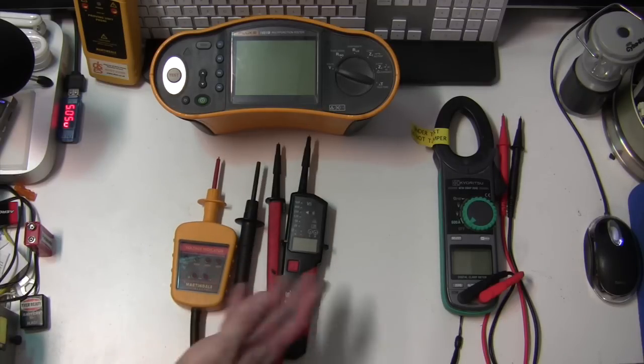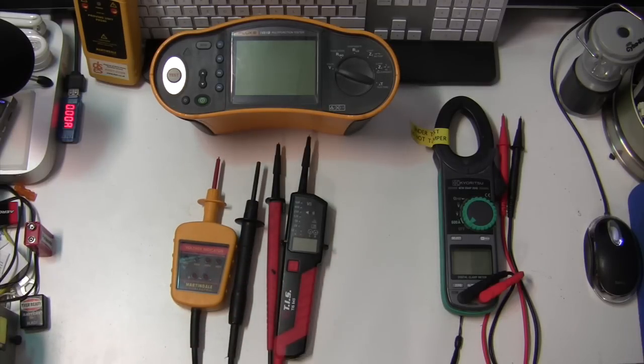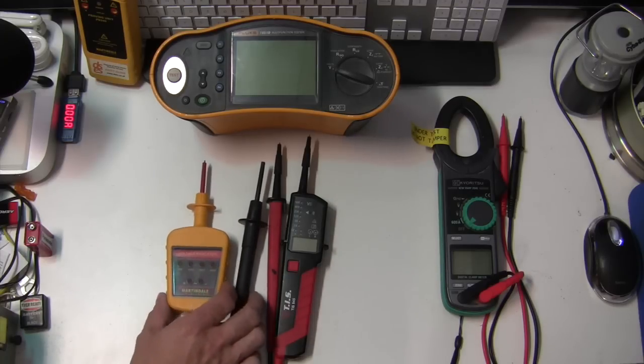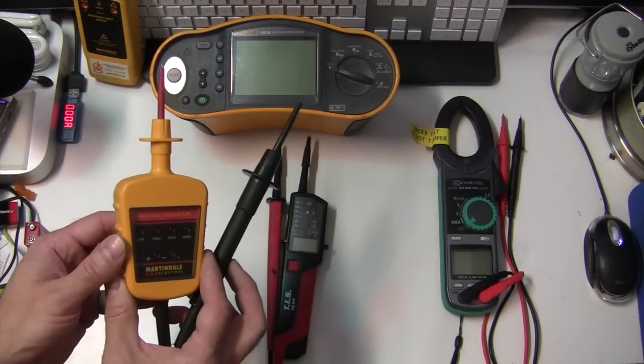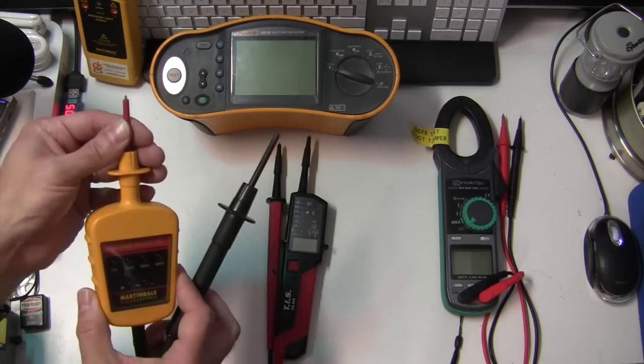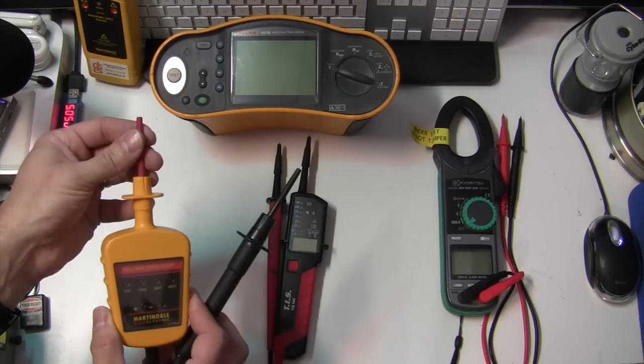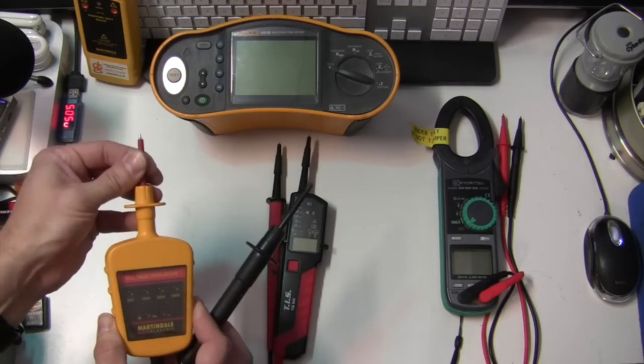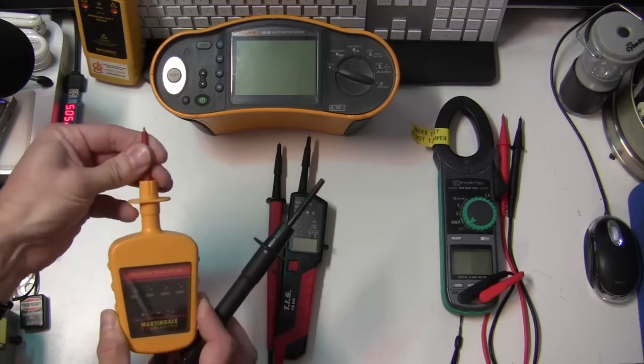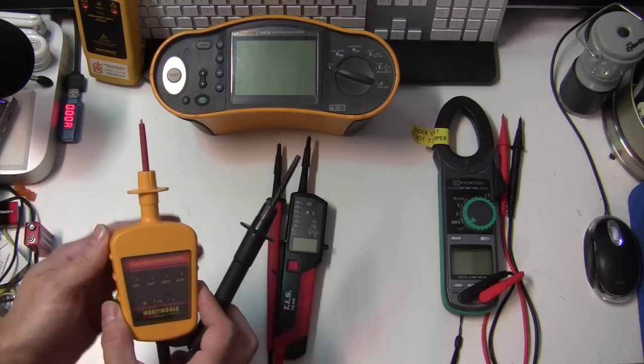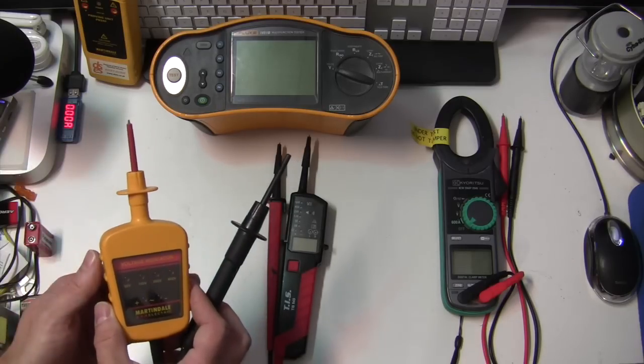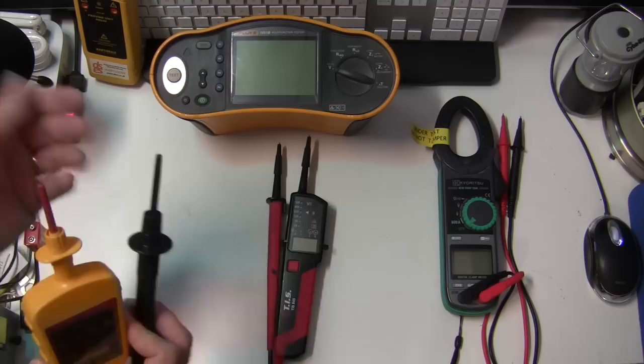I've got a couple of GS38 compliant voltage indicators here. This Martindale one is a plain and simple instrument for measuring up to 400 volts, with no whistles and bells, but with rather nice spring-loaded probe ends that can be kept shrouded or retracted to expose the tips if you prefer.